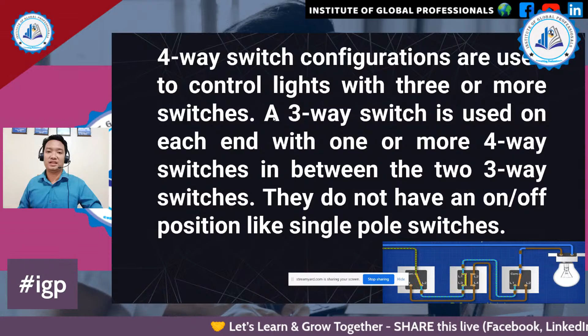We cannot directly use the four-way switch as a neutral or hot wire connection. It serves only as travelers for the three-way switches installed in a circuit. Four-way switches have four terminals, each with two pairs of travelers, one pair usually black and the other pair brass colored. A three-switch configuration will have two three-way switches, one on each end, and one four-way switch in the middle.